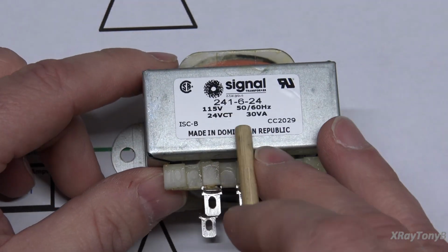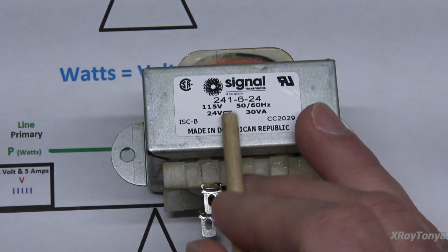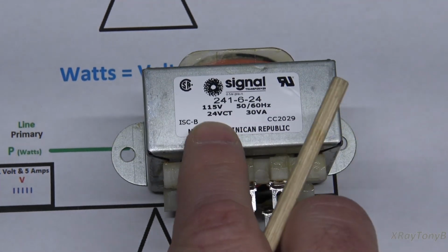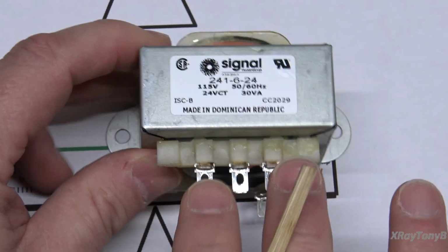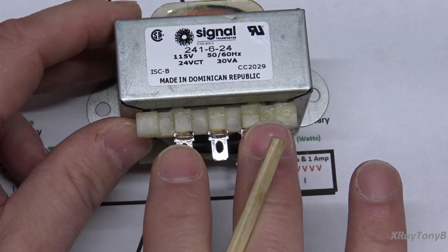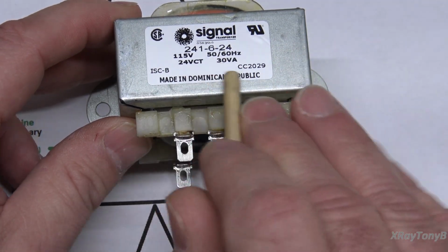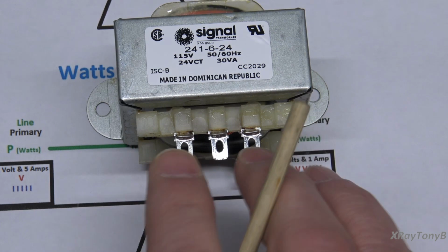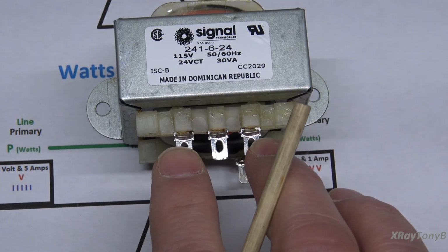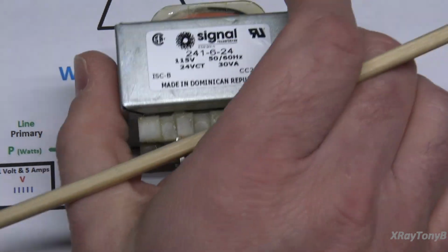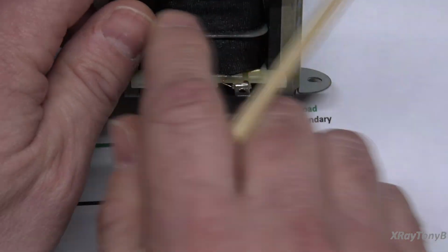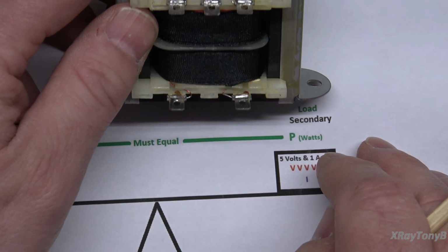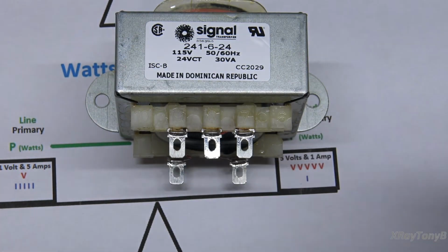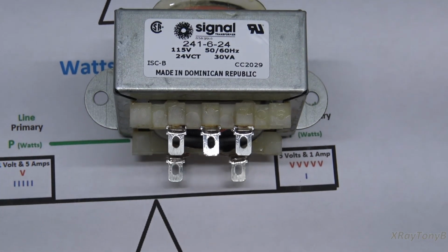So if we look at 30 VA at 24 volts, if I connect a 1 amp load to this that draws 1 amp, I'm already using 24 VA. So I really can't drive this much more than 1 amp. Because as soon as we start getting to that VA max, number one, the transformer is going to saturate. Number two, this winding is going to get very, very hot. Because remember, there is loss in this transformer that turns into heat. And those windings are going to get hot because of the current flowing through them. They act just like a resistor, right? They're wire.